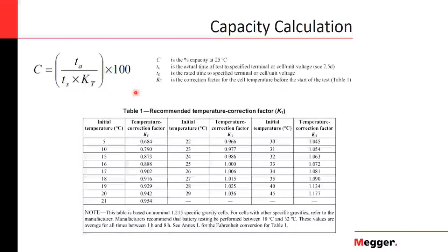By plugging all of these values in and multiplying that by 100, you obtain the capacity. So very basic: it is the actual time over the expected time, and the correction factor for temperature. And the correction factor table is provided in the IEEE standard for each of the batteries. It's the same one, so you can use that information to do your calculations.